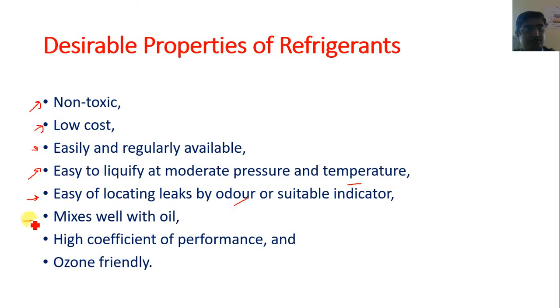It must also mix well with oil in the case of a reciprocating compressor, or the sealing oil. It also has a high coefficient of performance, meaning the value of COP is high. And it should be ozone friendly. So these are all the desirable properties of a refrigerant.